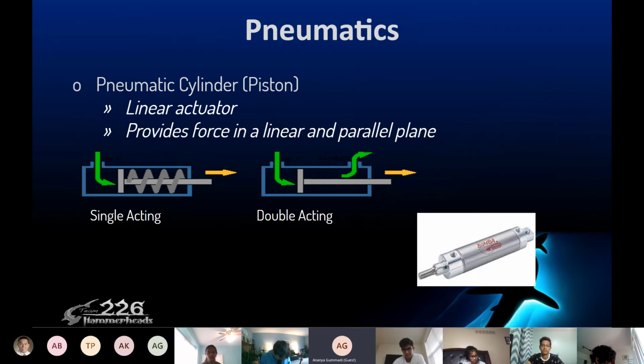These single-action valves have one input port, which is the air from the regulator, and one output port, which is connected to the cylinder, and one set of wires which connects to a valve port on the pneumatics control module. The single action valve will open when power is applied and has a spring that closes the valve when power is not applied, and the pressure is only present at the cylinder when the valve is open. When the valve is closed, however, the output port that is connected to the cylinder is vented to the atmosphere, allowing the air in the cylinder to escape.